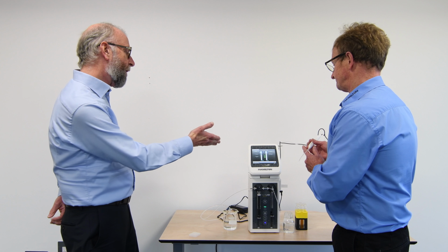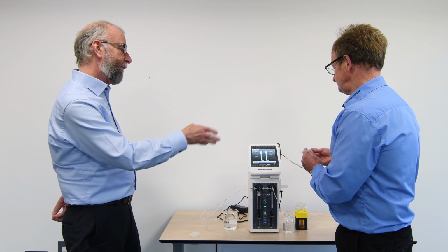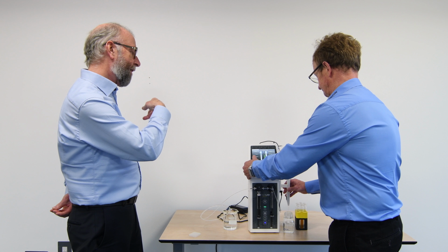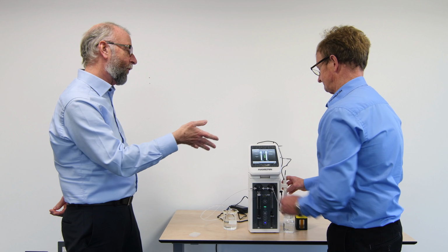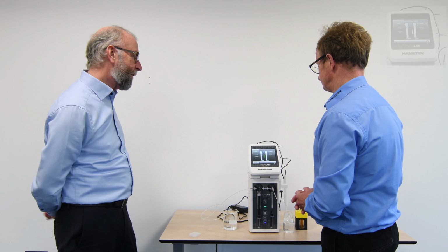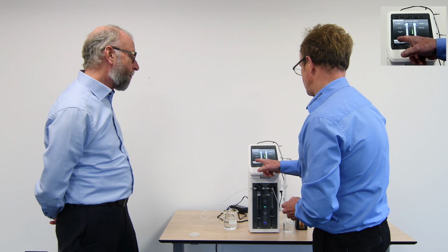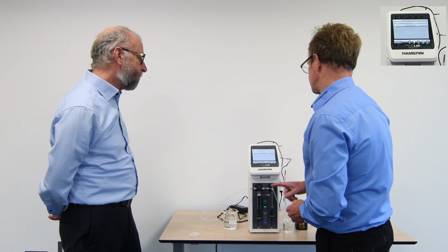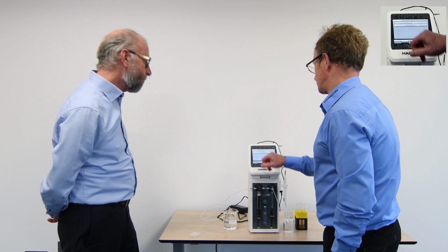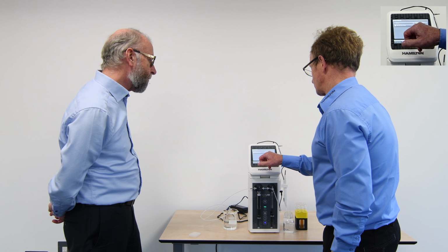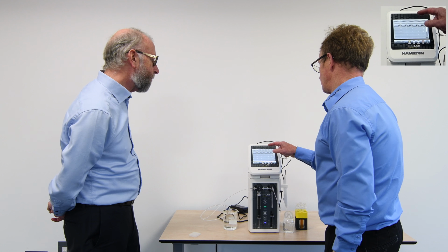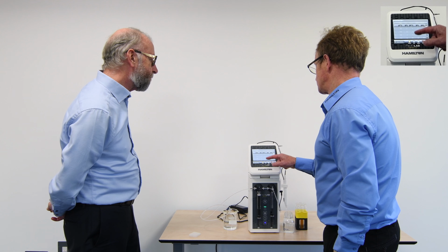Okay, and if I now wanted to edit that, so I felt happier with having a larger wash volume, can you show me how to do that, please? Yeah, sure. So if we go back into our custom methods, and now we highlight that particular method here, we have an edit function, and we can go to that. Okay. And we're able to go through each of the stages that we're looking for.